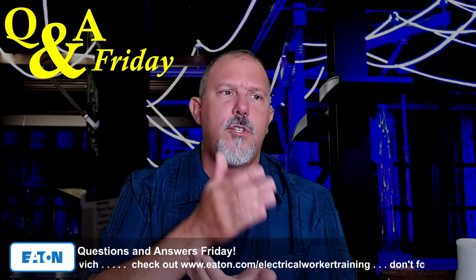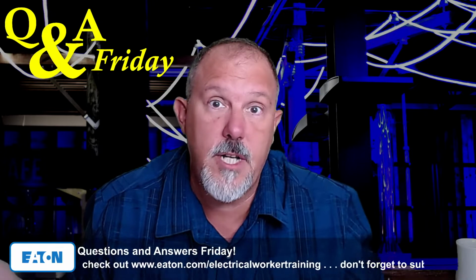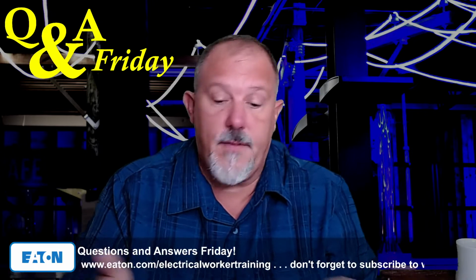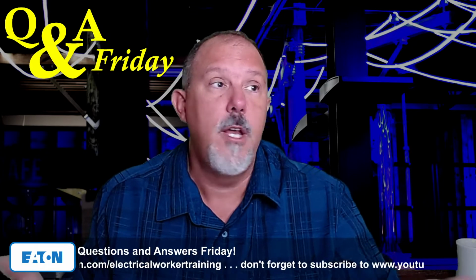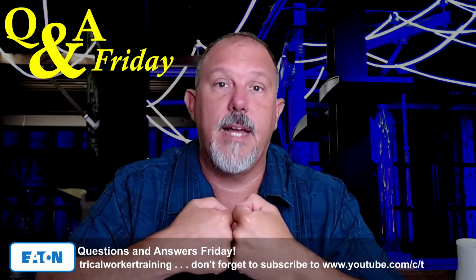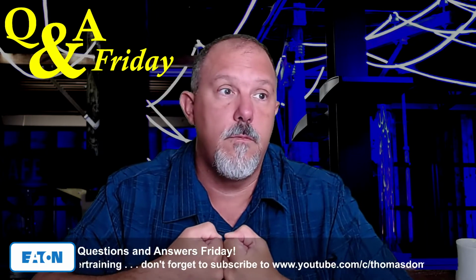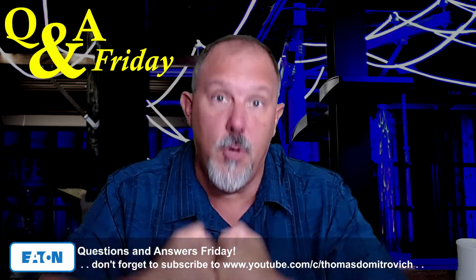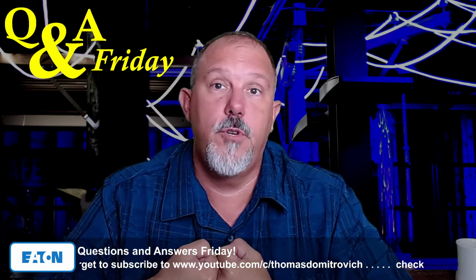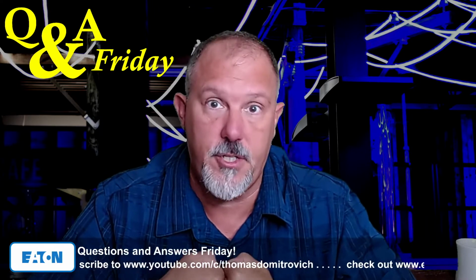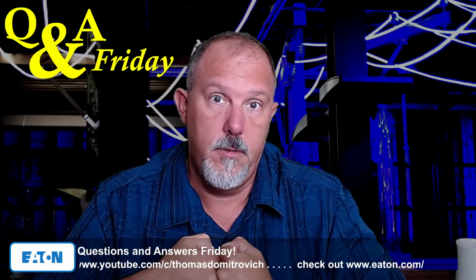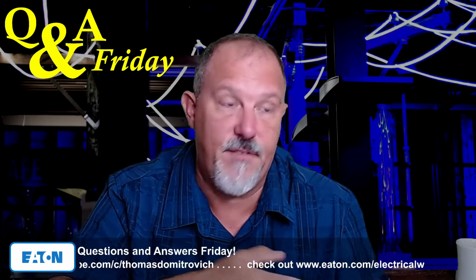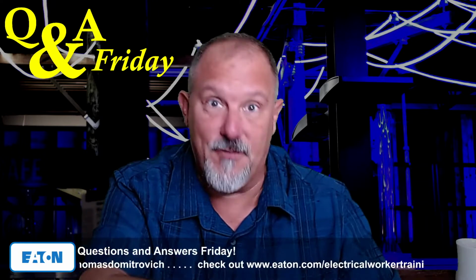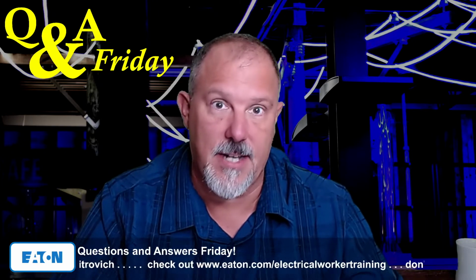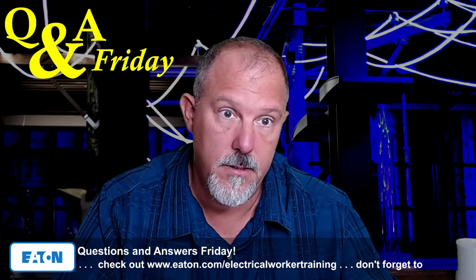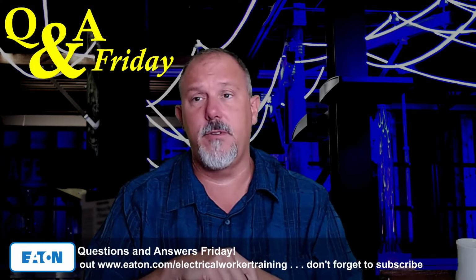If my circuit breaker, well, let's talk selective coordination. If I selectively coordinate two breakers together, the upstream breaker is going to hold its contacts closed for the maximum available short circuit current, which will be much more than any locked rotor current that you have on a motor. I still need to apply 240.87. In fact, that's where you really should have 240.87, regardless of the size of the overcurrent protective device. So no, I don't necessarily agree with that.